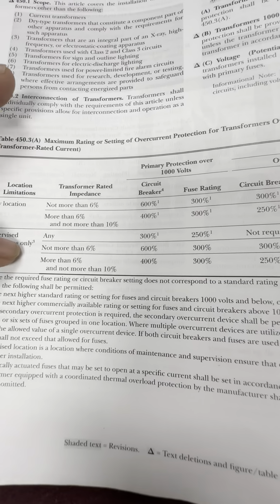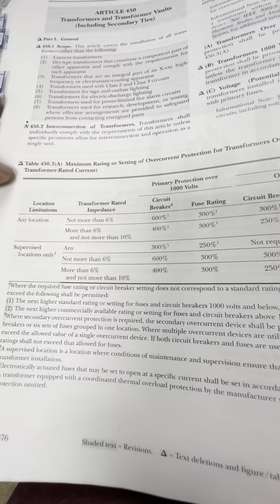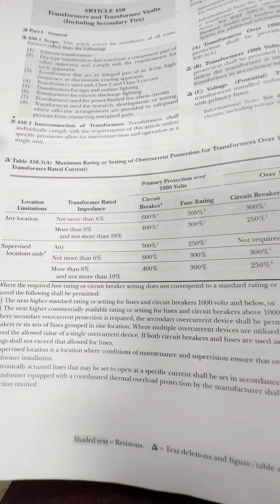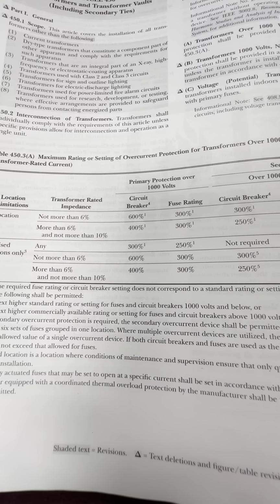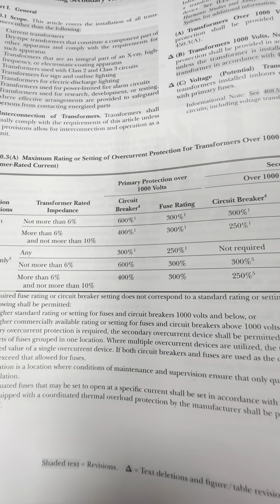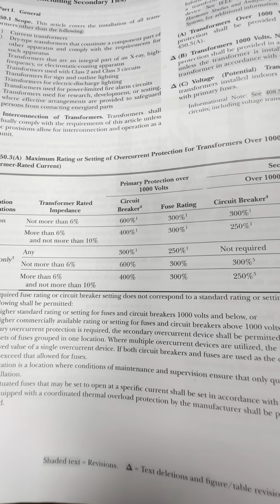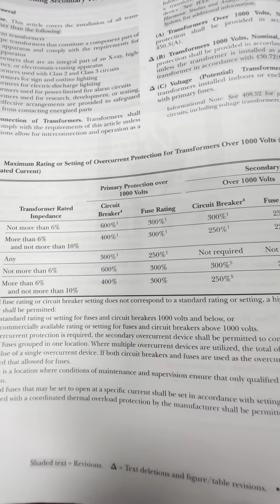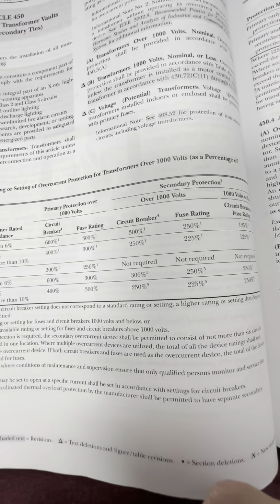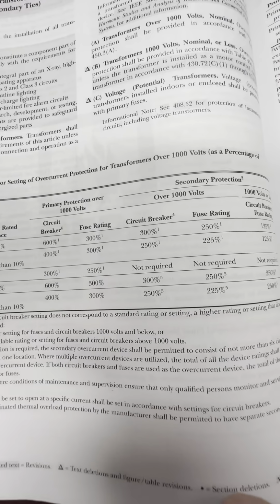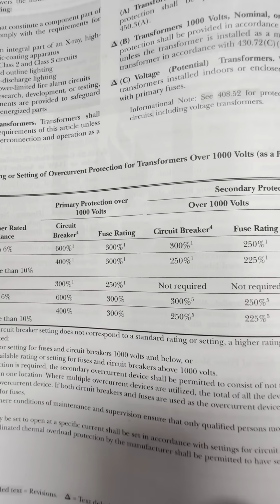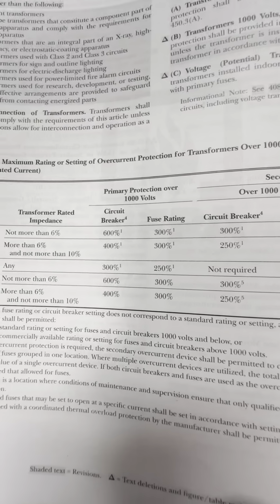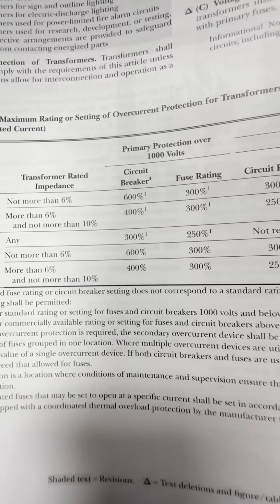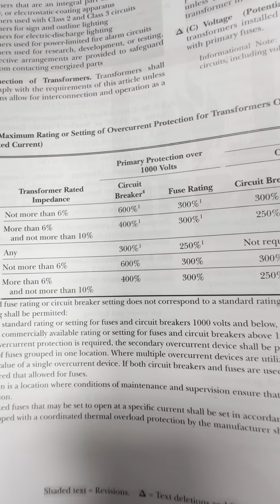Our next column is our primary protection over 1,000 volts. So we're not quite there yet, but we're getting there, but we can go ahead and look up this information. And it breaks down into 2 sub-columns, depending if you got a circuit breaker or a fuse. So I'm just letting y'all know that we do have circuit breakers on both the primary and the secondary side. So looking there at the circuit breaker column, what percentage do y'all see? 600. So not quite to the primary just yet, but we'll go ahead and record 600% for it.